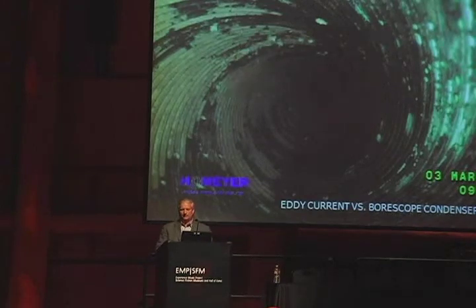But you can see that this tube is heading into some disasters in a couple years, because the water treatment program is not really effective. You're either going to scale it up, or you have some copper corrosion, which is eventually going to go through the copper itself, which the eddy currents will pick up. The question is, will you do the next eddy current before you have a tube failure? And you're seeing biological activity, which we'll talk about, biologically influenced corrosion.